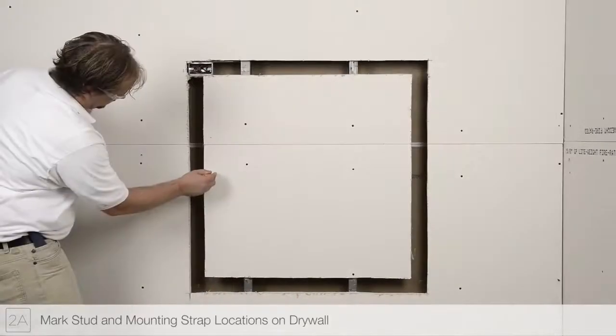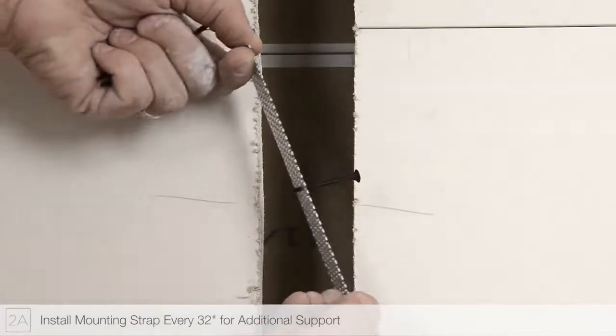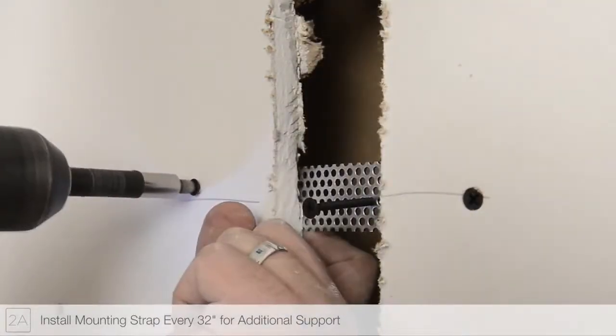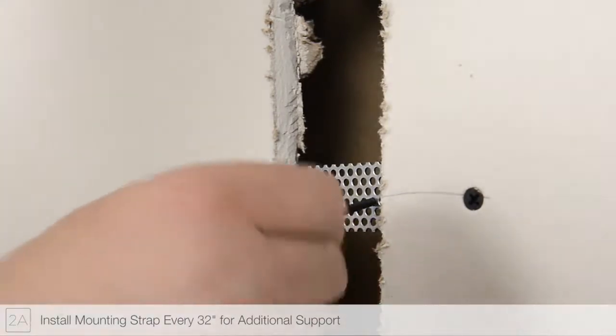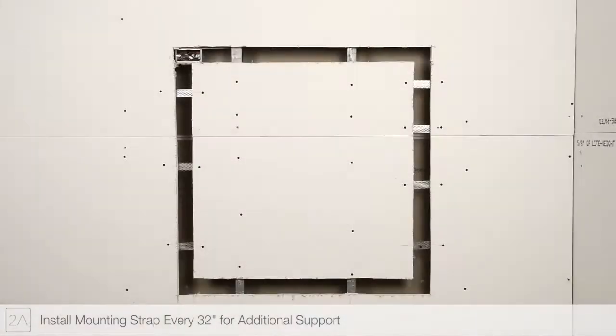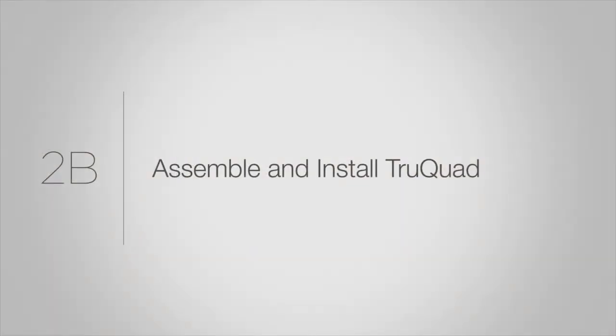Mark the stud and mounting strap locations. Install mounting straps every 32 inches along the installation area for additional support, where there is no stud or joist to support the channel. Step 2B.